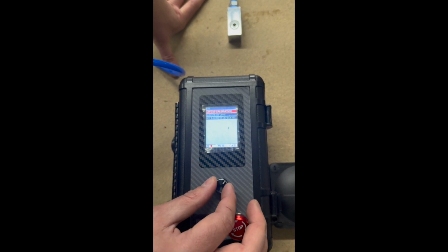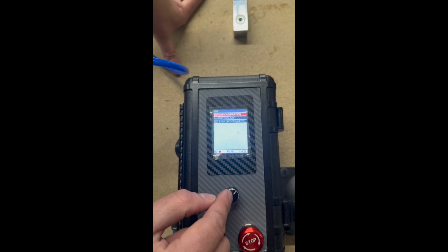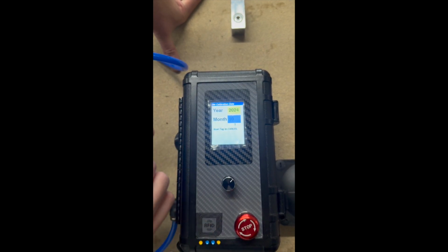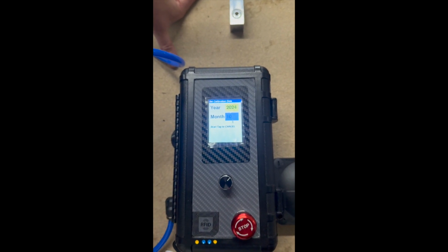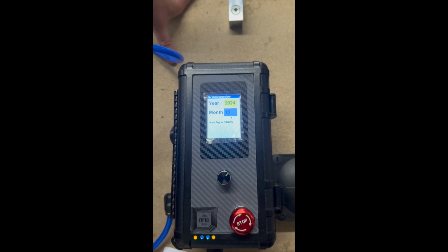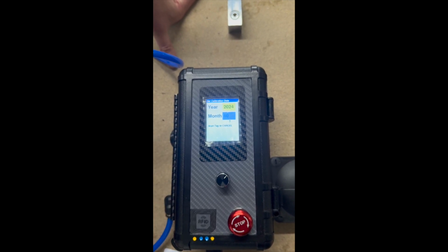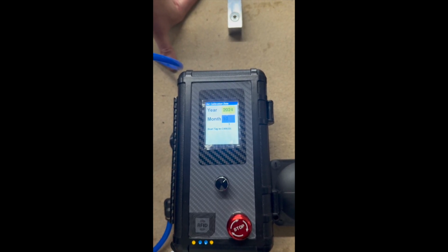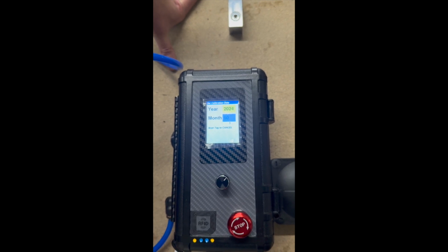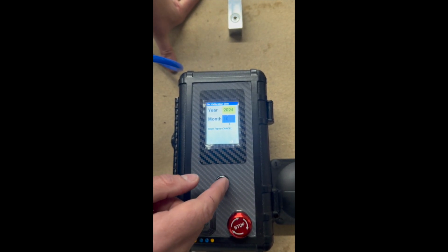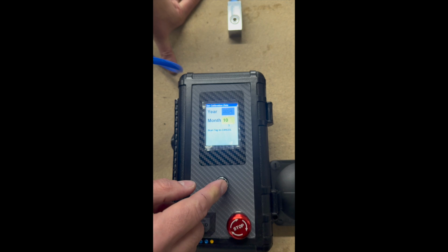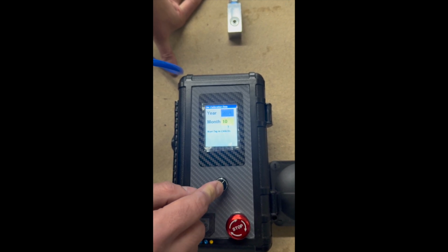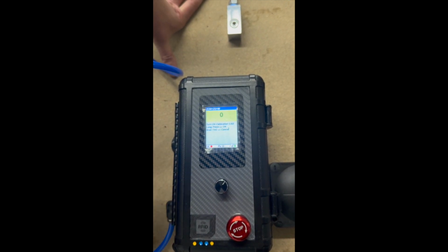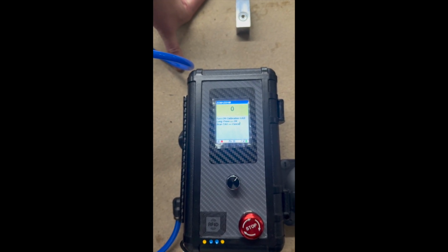And I'll show you how to do the calibration. You come on the CO gas calibration. I'll press and hold for a couple seconds, and I'll see this menu. First, it's asking me the calibration date. This was calibrated in 2024, 10th month of 2024. So I'm not touching anything, so I'll just skip that part. And then next, I'm seeing the CO. Right now it's reading 0.